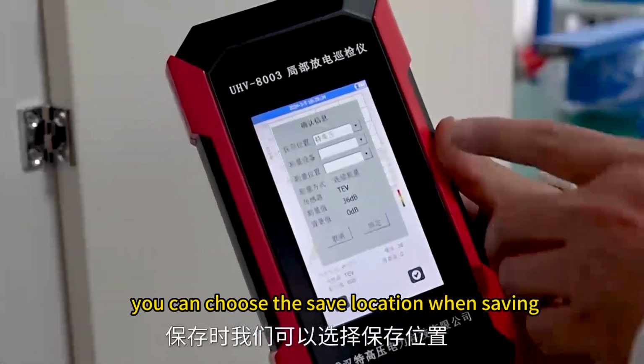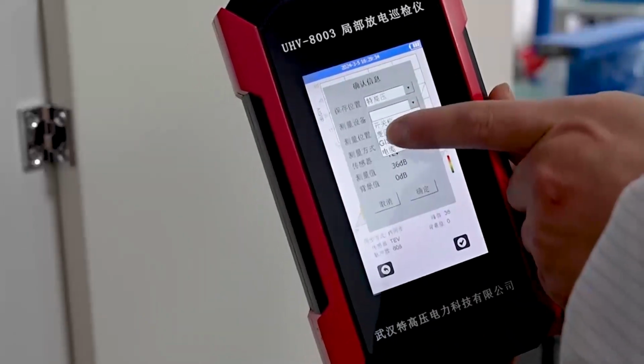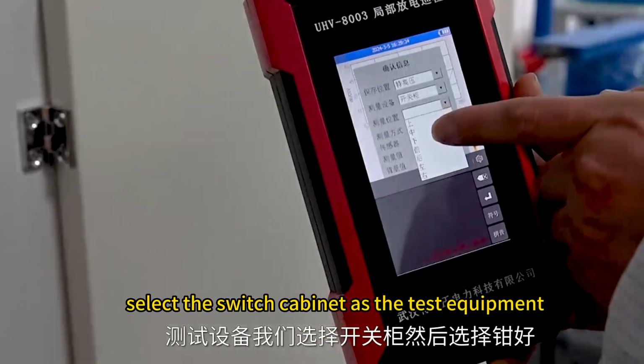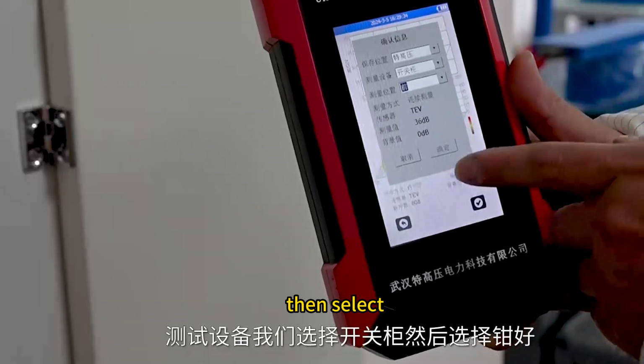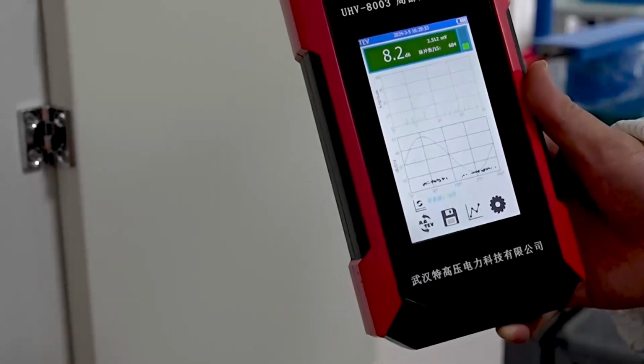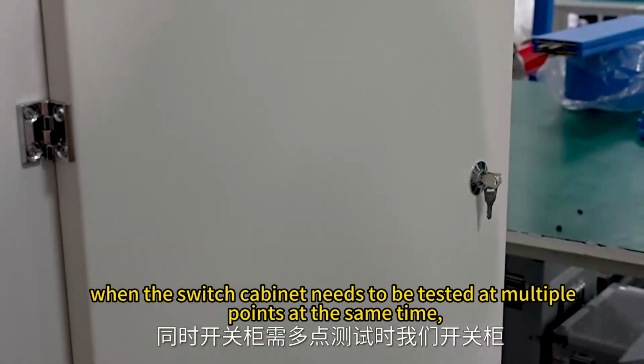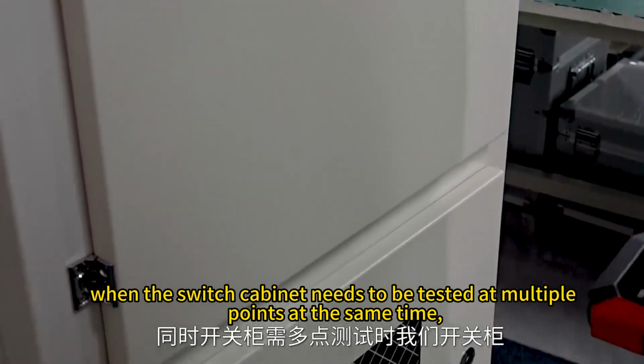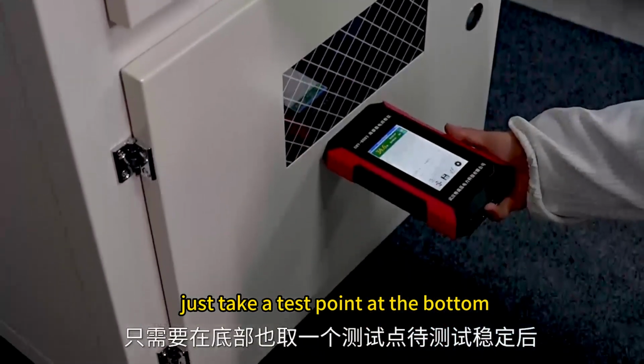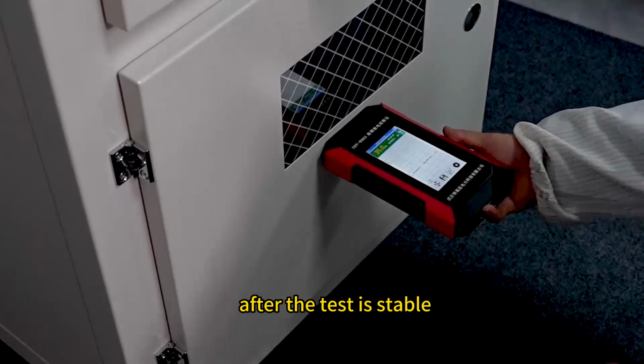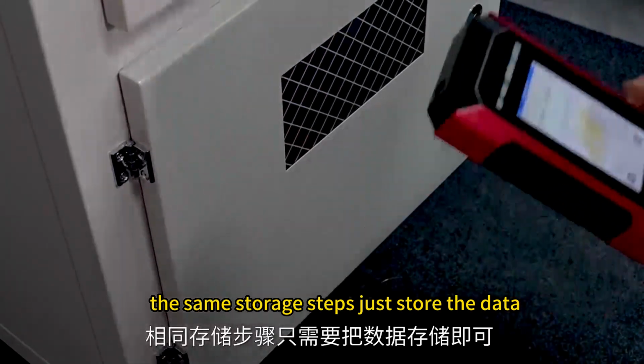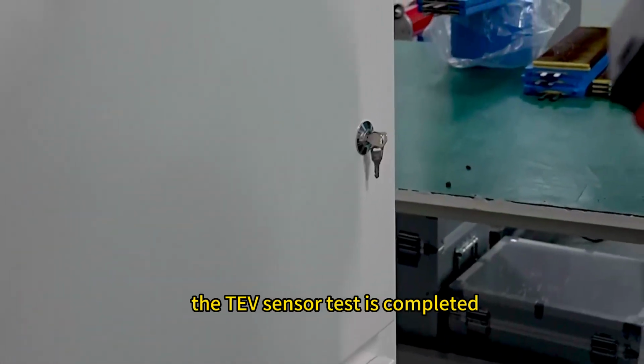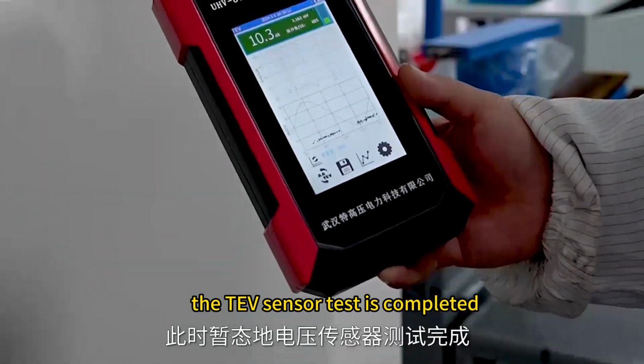You can choose the save location when saving. Select the switch cabinet as the test equipment. Then select, and click OK. When the switch cabinet needs to be tested at multiple points at the same time, just take a test point at the bottom. After the test is stable, the same storage steps, just store the data. The TEV sensor test is completed.